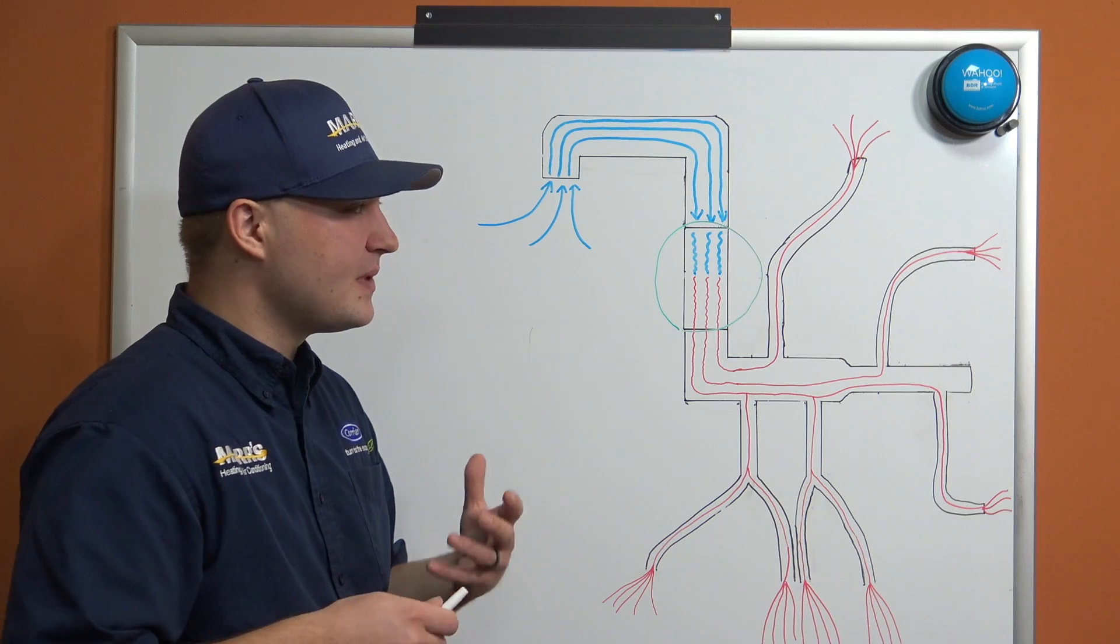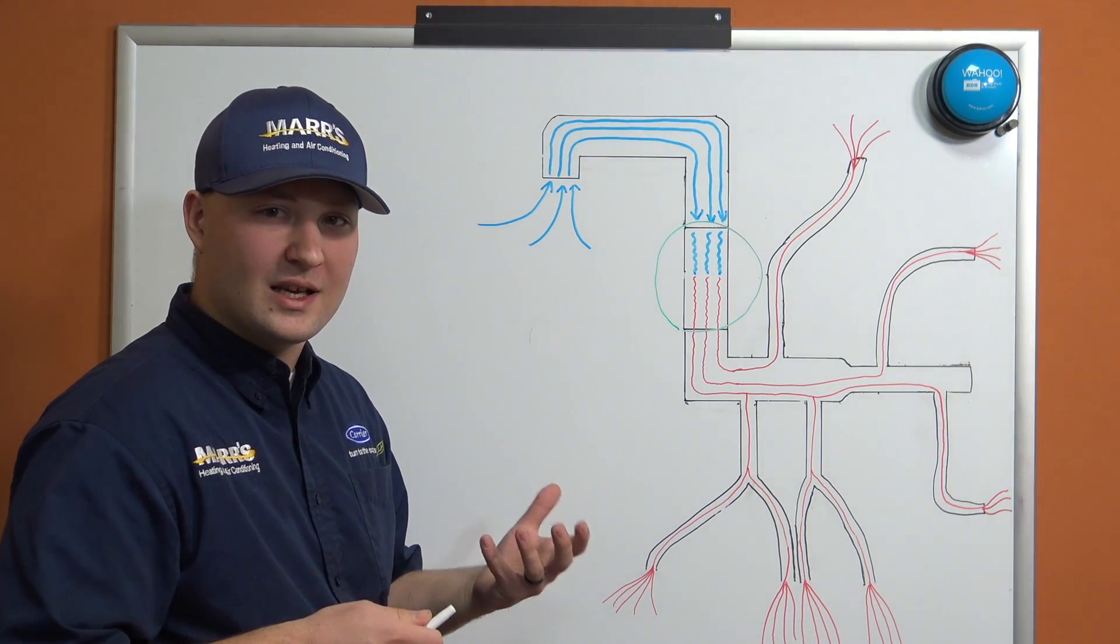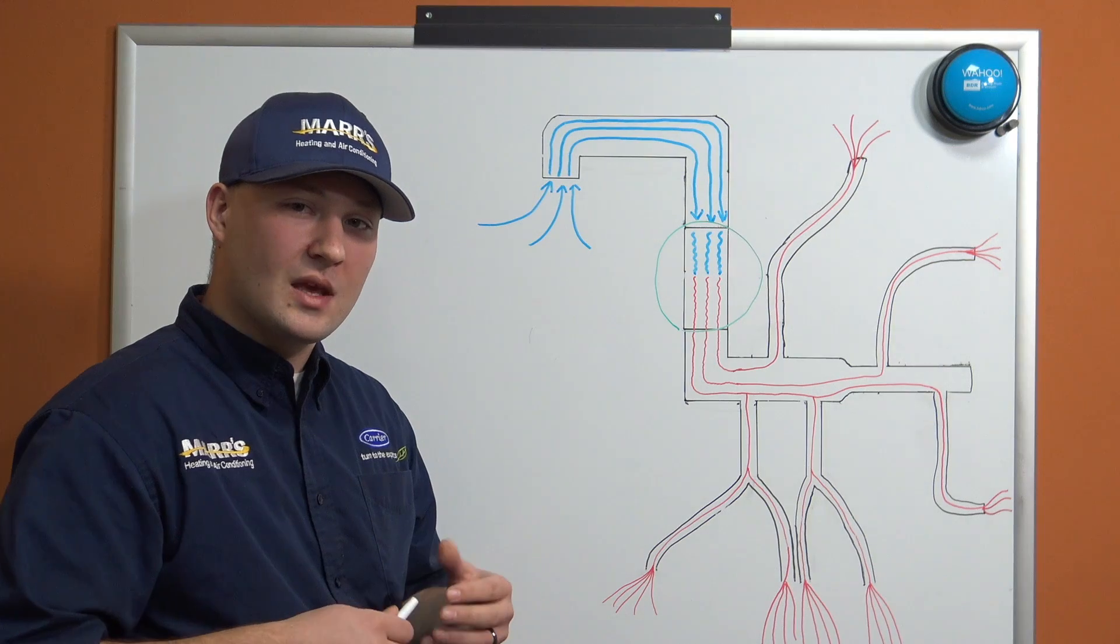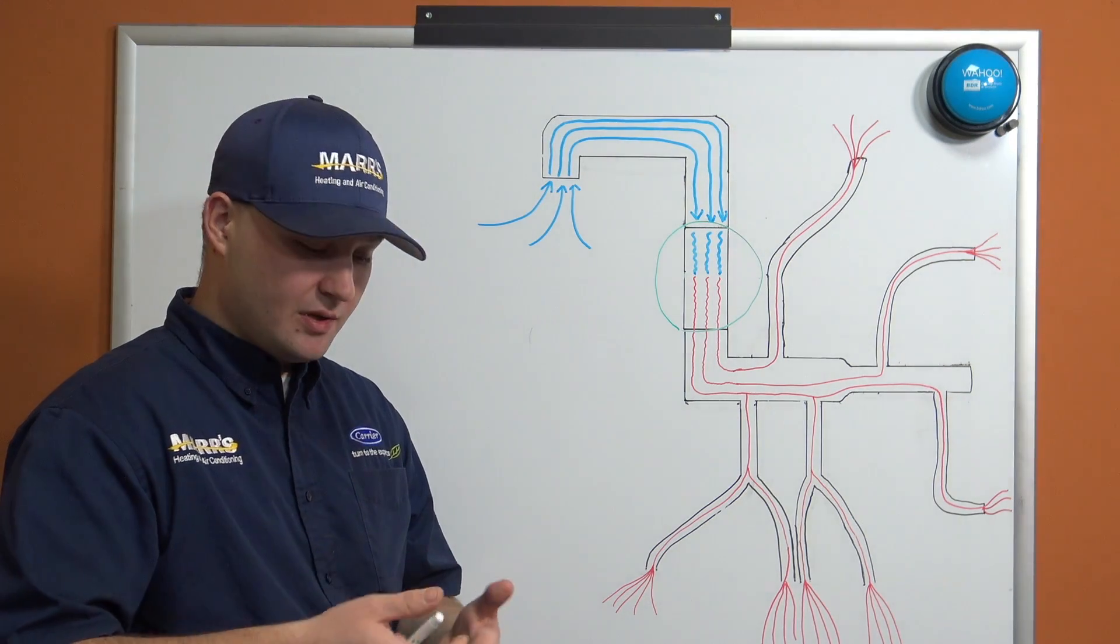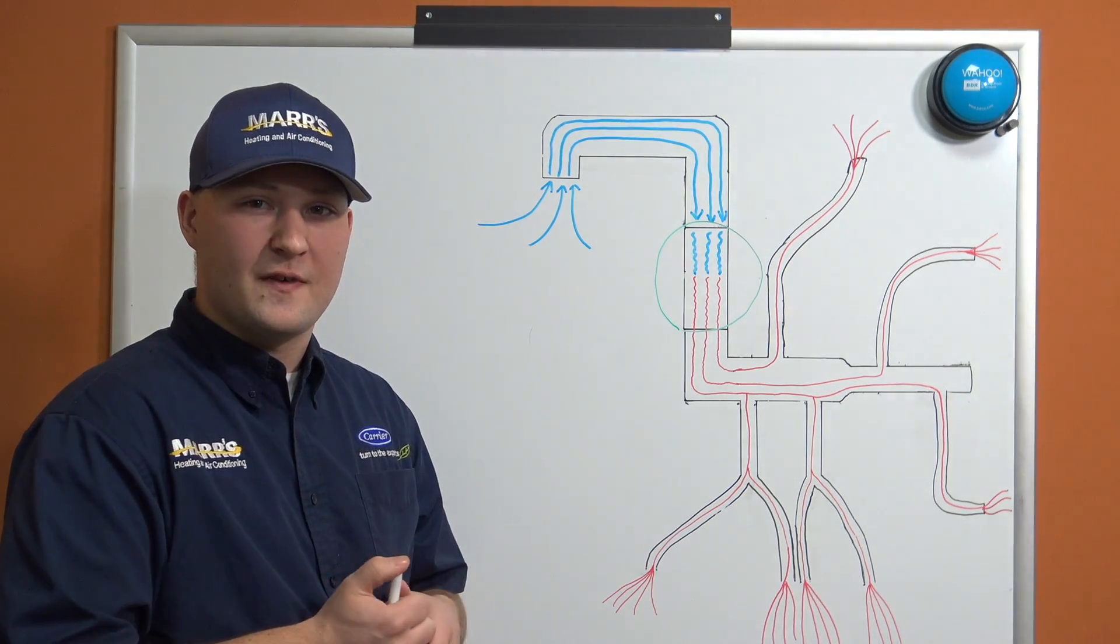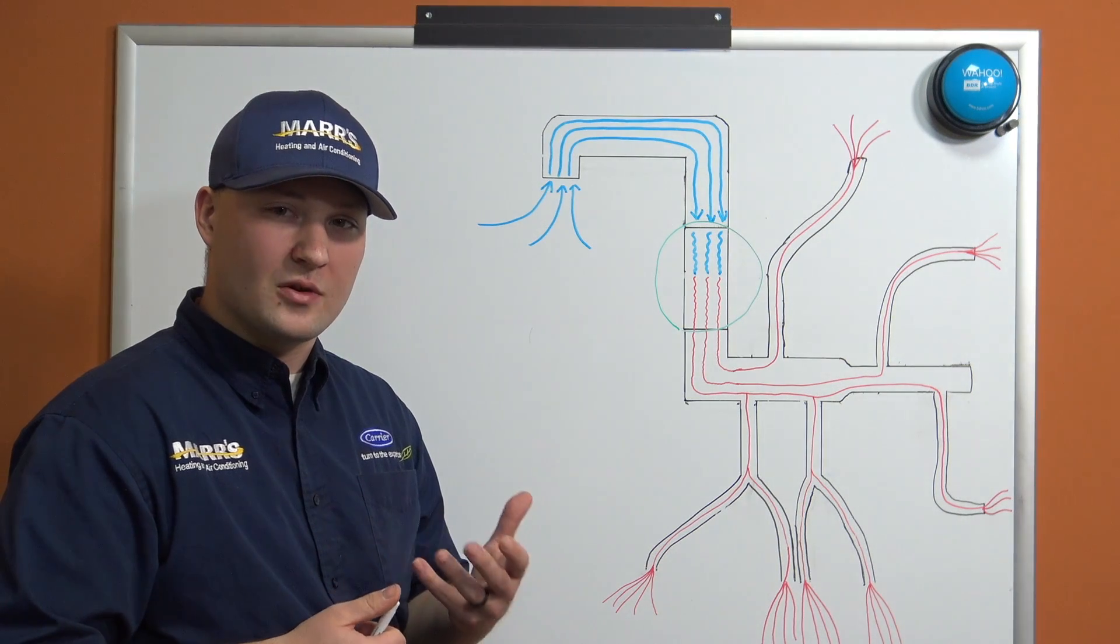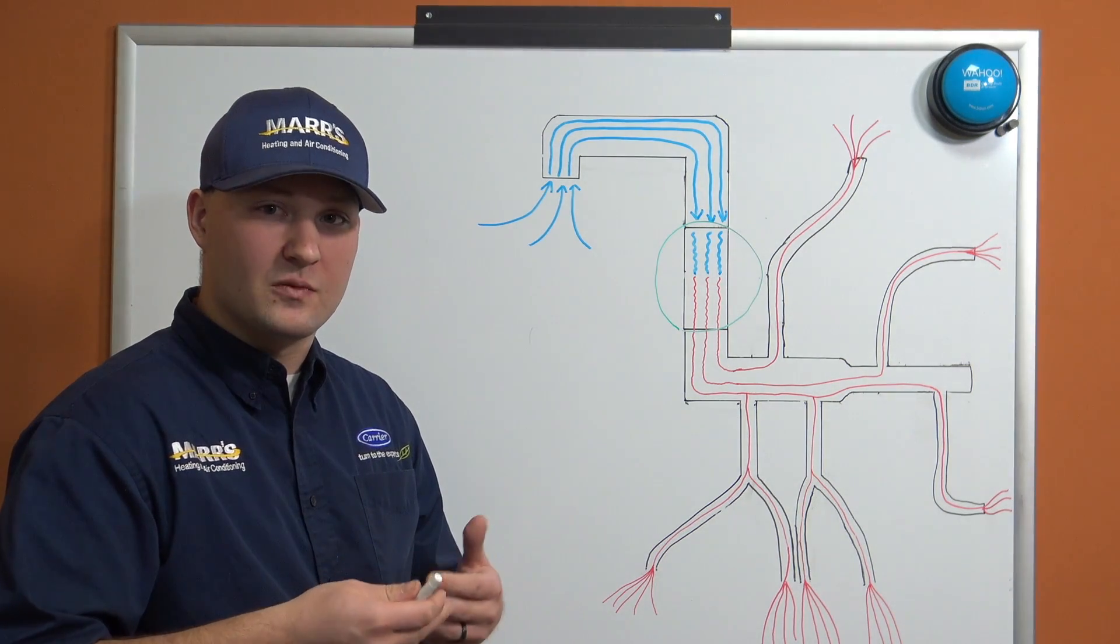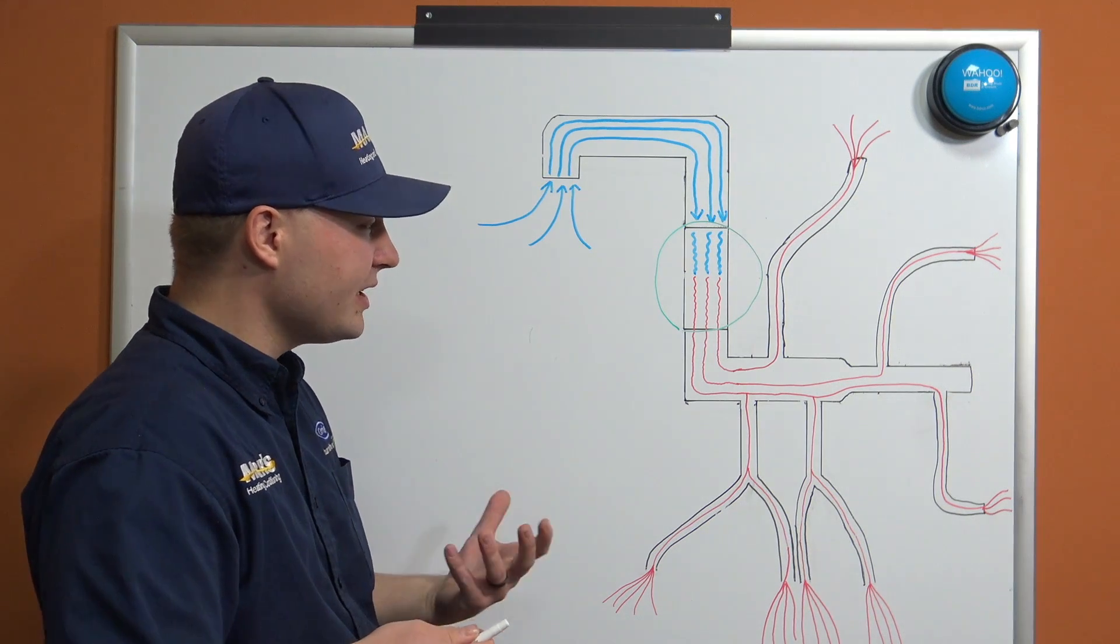We're going to correlate that to the charts that are provided by the manufacturer, and that'll tell us whether or not we're going to fall within the given range that we need to fall in. Things that can affect static pressure, just like blood pressure—if you think of our duct system as arteries, we don't want clogged arteries.